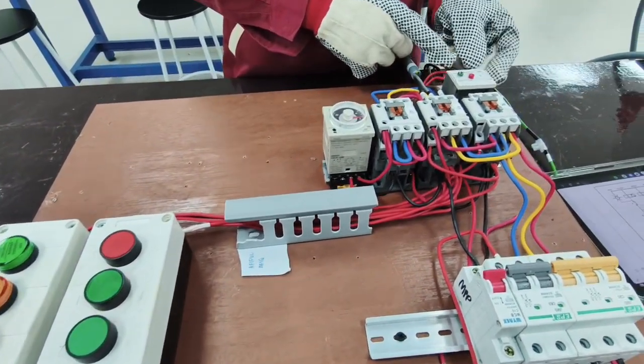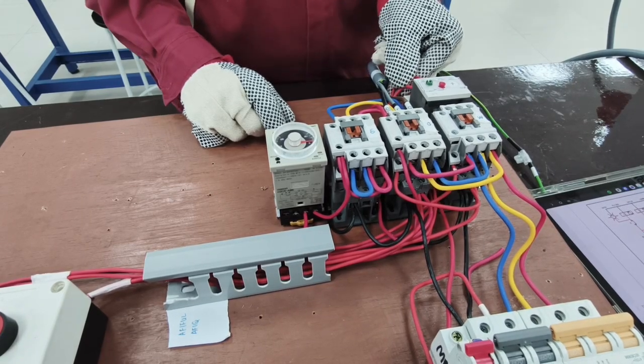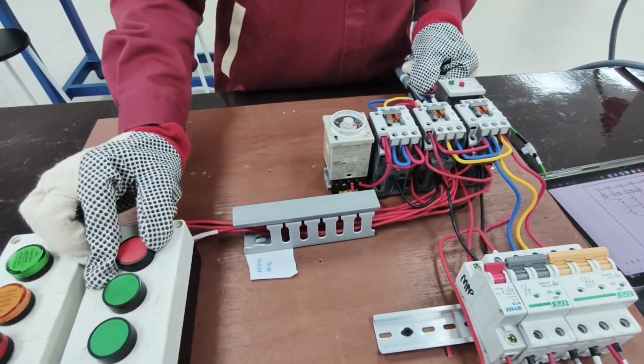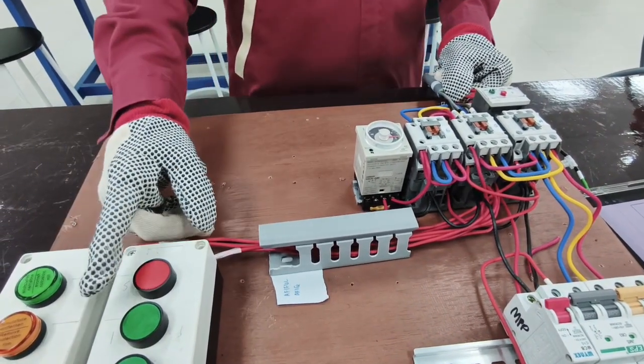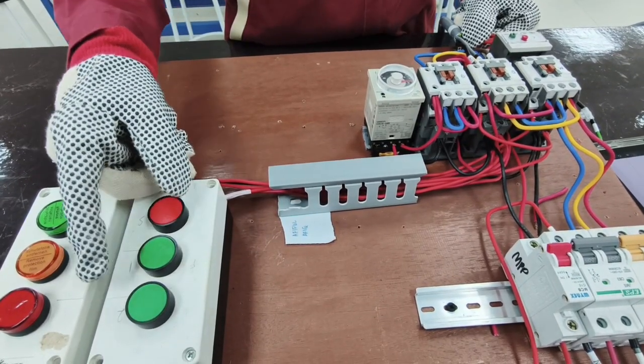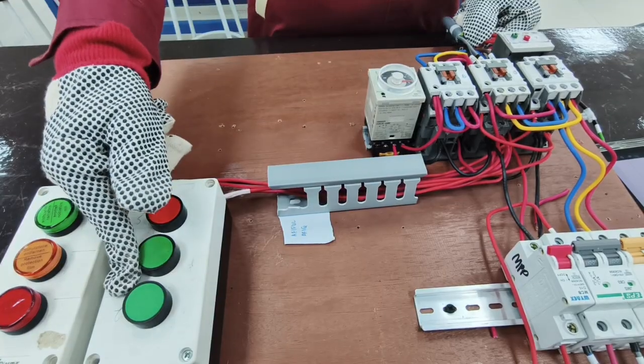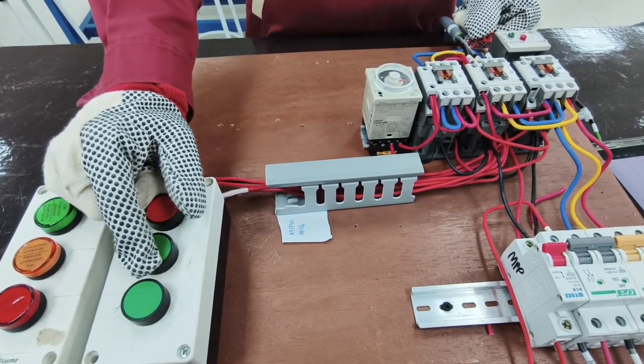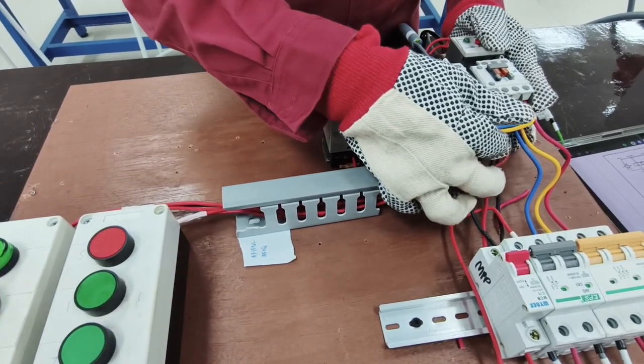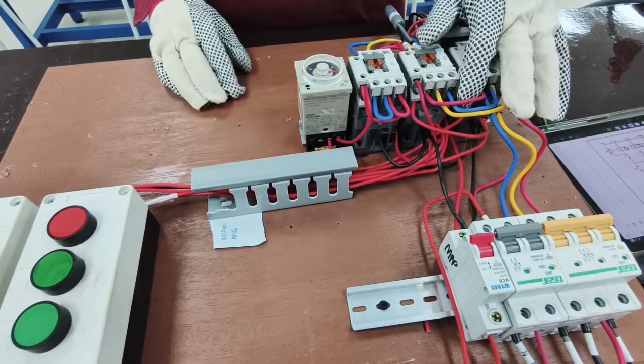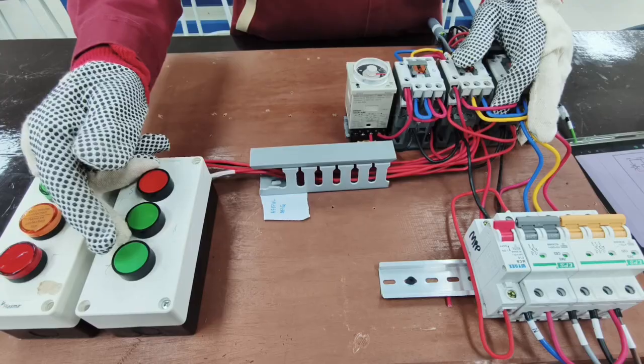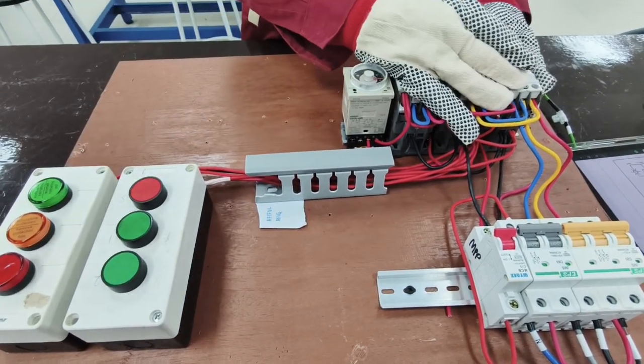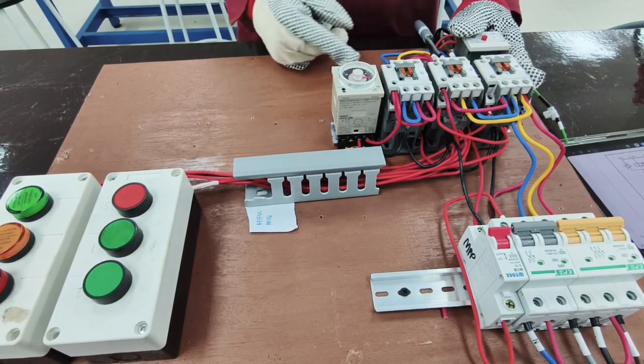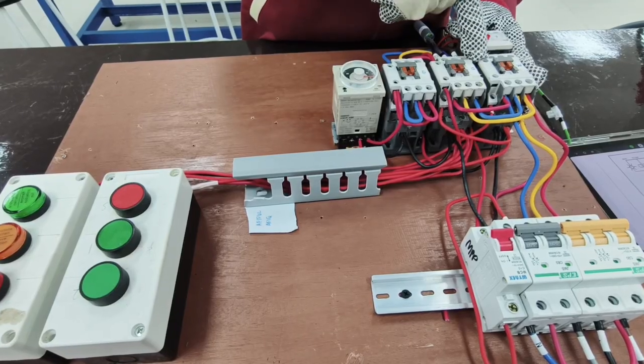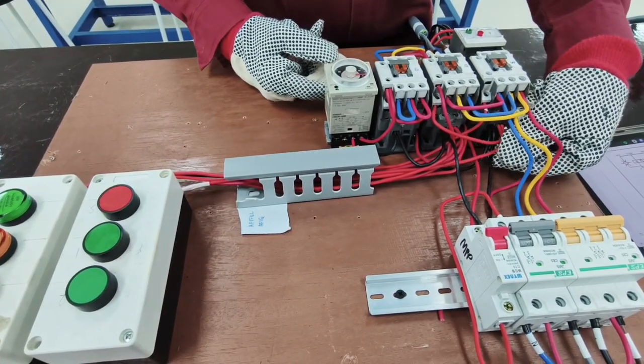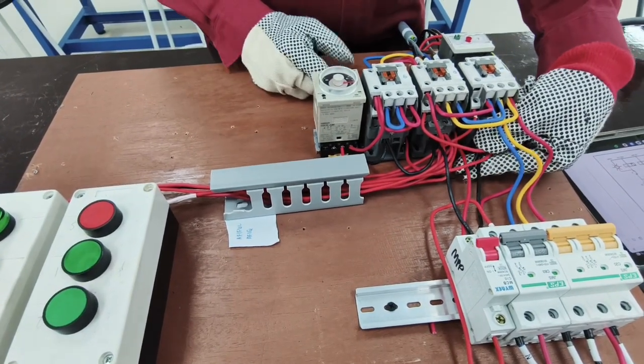For the normally closed, from 96, we will go to the stop button first, which is a normally closed contact. From the stop button, it will connect to the start button command. From the start button command, we need to put a latching to the main contactor at connection number 43. So outgoing from the start button, which is normally open, we also need a latching to the contactor at point number 44. From outgoing, we took from the 44 to the A contact of the main circuit, and then the B contact we go to the neutral.